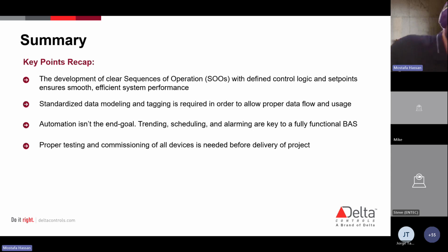To summarize, we started off with the sequence of operation: selecting the correct control logic, the correct set points, and the proper field devices necessary to control the system. That's going to help your system operate properly. We went through the sequence of operation of all the systems, made sure the logic made sense, and took safety into consideration. Then we talked about standardized data modeling and tagging, which is needed in order to actually use the data after we automate the building. And again, automation is not your end goal. Throwing in the hardware and making everything run on a cycle is not the end goal. Trending and scheduling are the key to a fully functional BAS. When you trend points, that's where you start indicating future failure. That's when you start knowing if your system is actually operating at the intended set points or conditions. Last but not least, proper testing and commissioning of all devices is needed before delivery of a project.